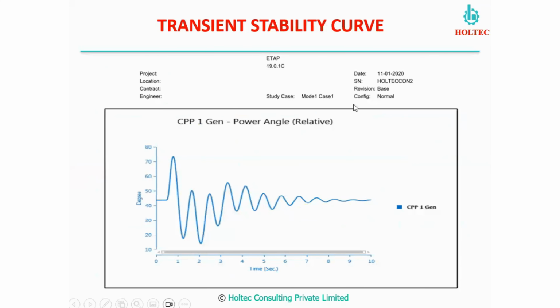This is a power angle curve which we discussed in the previous slide. Here you see the fault has occurred, and within 100 milliseconds or 150 milliseconds, whatever the clearing time, we have cleared it. This is my first swing, and it is below 100 degrees. This gives me first assurance that stability will be retained, and it is followed by a decreasing bandwidth of fluctuations, which means that after some time the system will become stable.